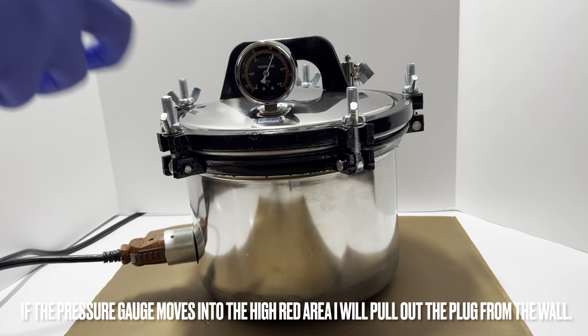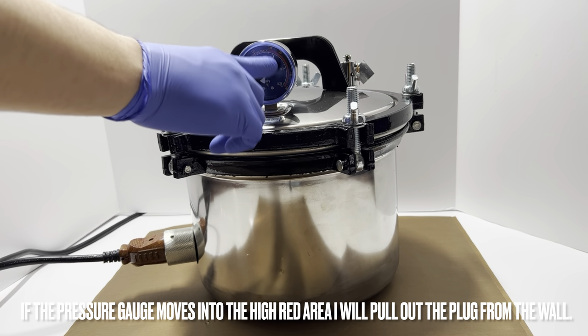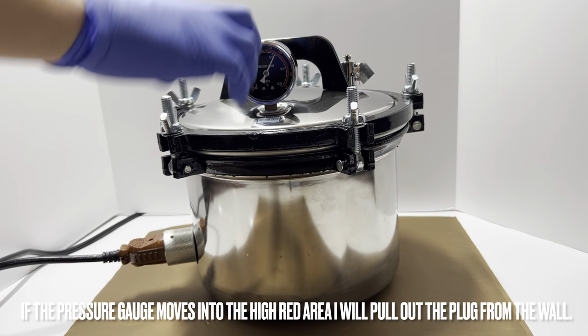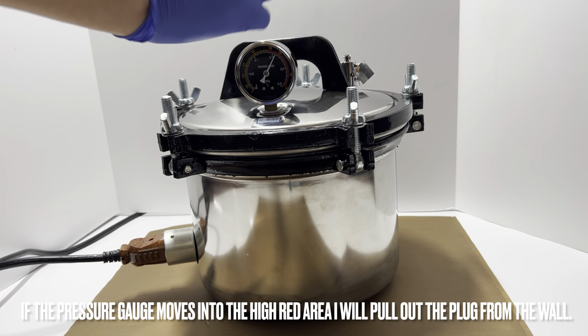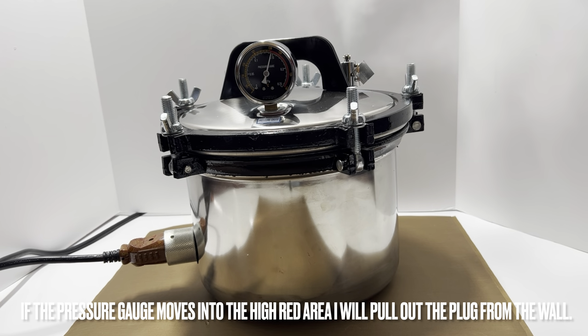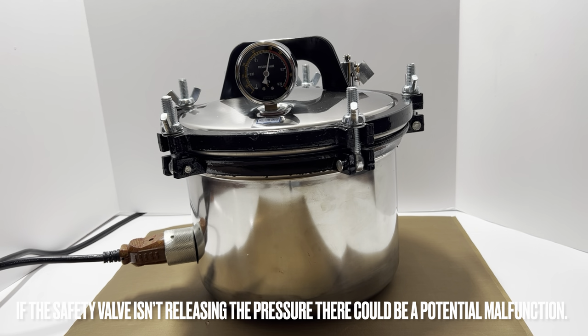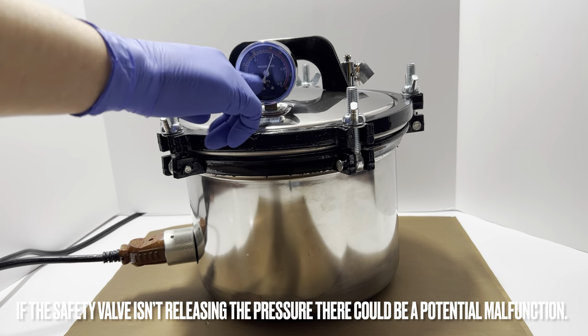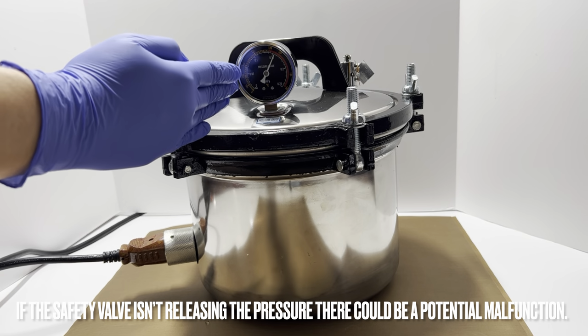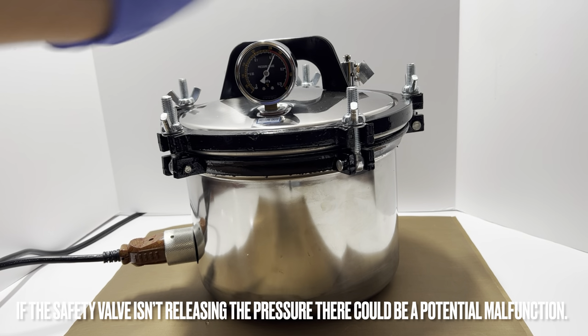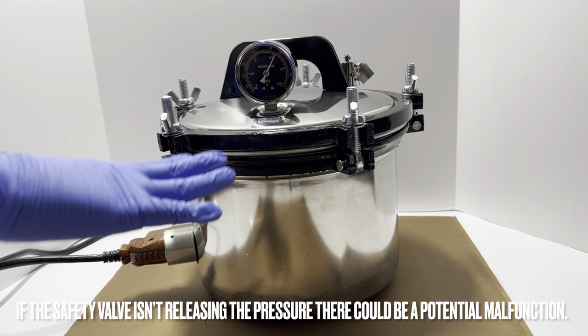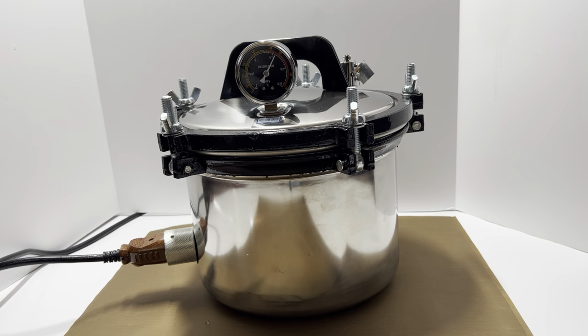Now, just to reiterate here, there's a gauge here that I'm watching. If this right here goes above a certain area that makes me feel uncomfortable, I'm going to pull that safety valve up and I'm going to pull the plug out. I'm going to cut the power to it. So I just wanted to reiterate, that's what you would do if these get out of whack and it's not at a steady temperature like it is right now. If it goes too high, pull the safety valve, pull the electricity, and let it go down to zero, let it cool down. But this is completely normal, what's happening right here.